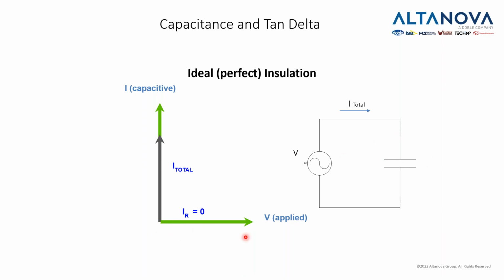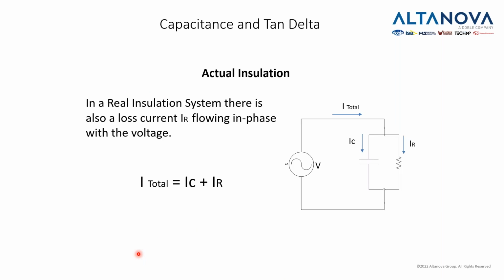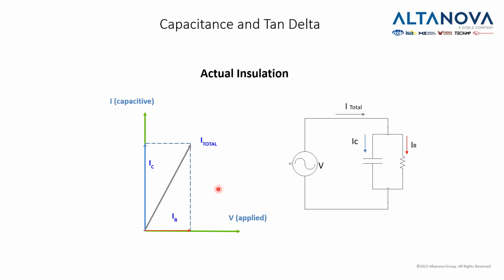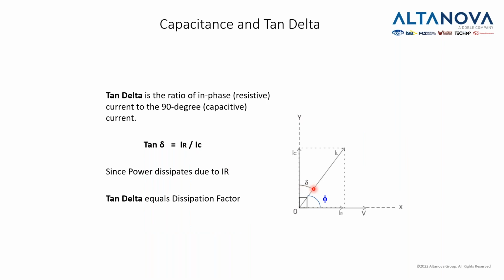In the capacitor, we see that we have a voltage and the current shifted by 90 degrees, but we know that there is no such thing as an ideal capacitor. We always have a resistance here in parallel, which adds this current. It is a very small current, but it is a measurable current. So long story short, we need to sum vectorially these two currents, and we get this total current. And then if we check, this angle delta here is what we are measuring.